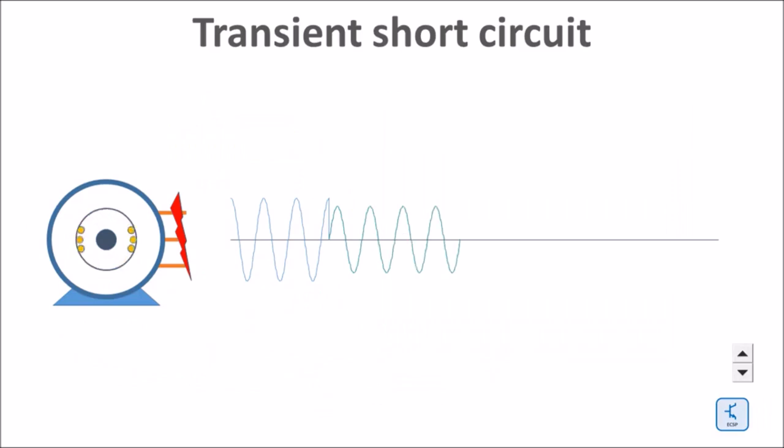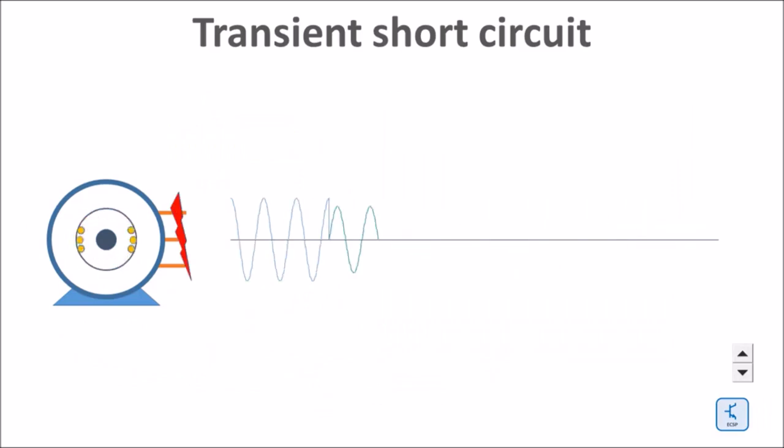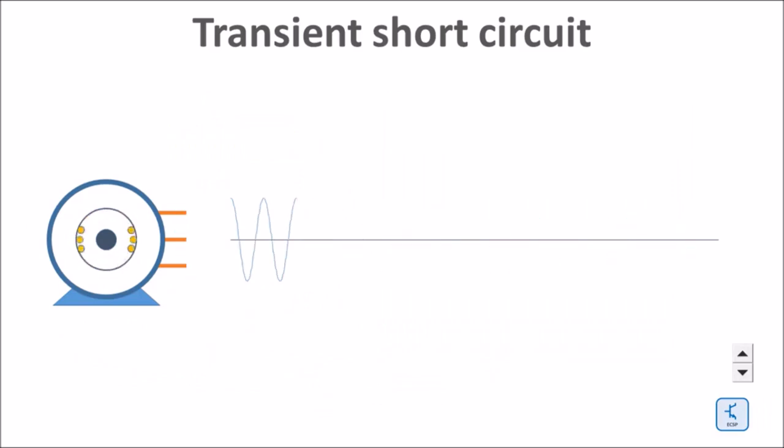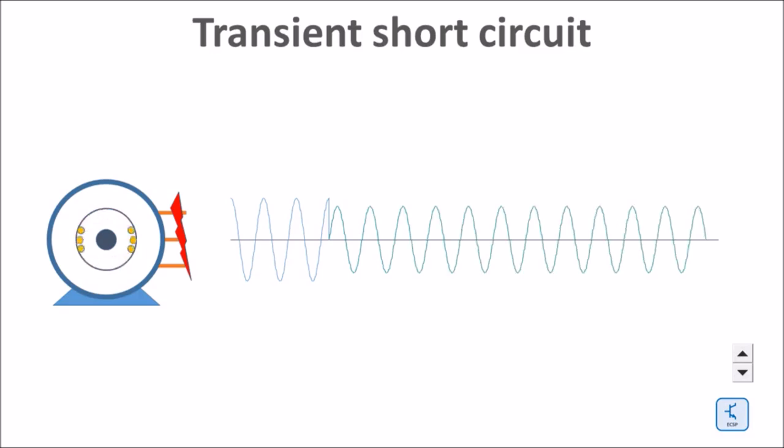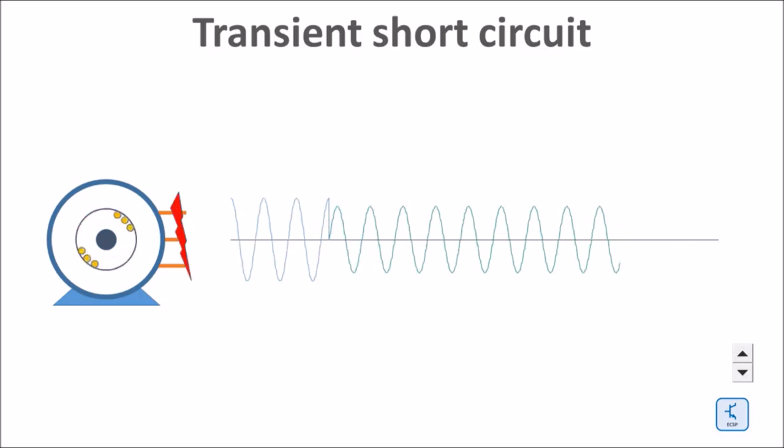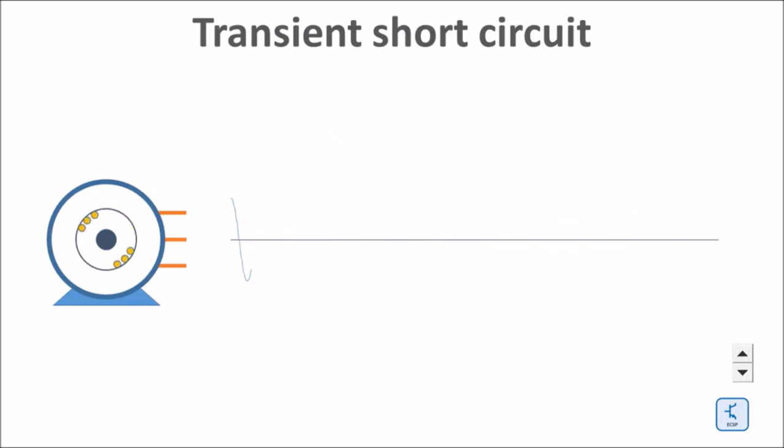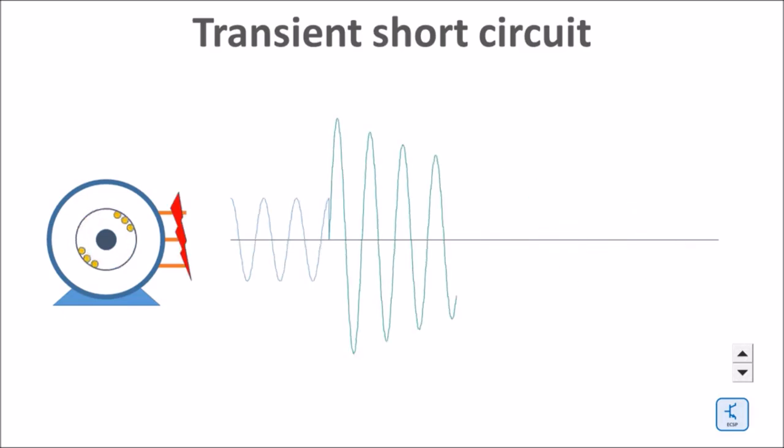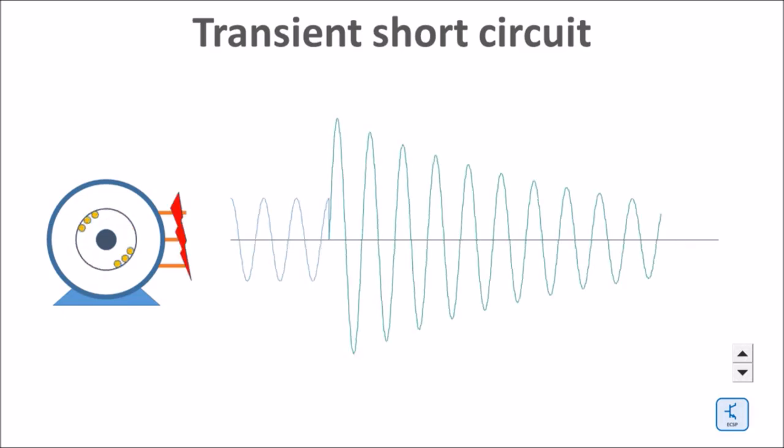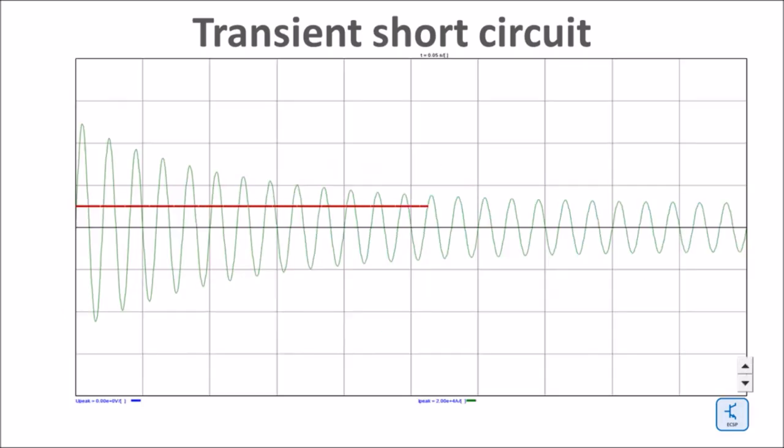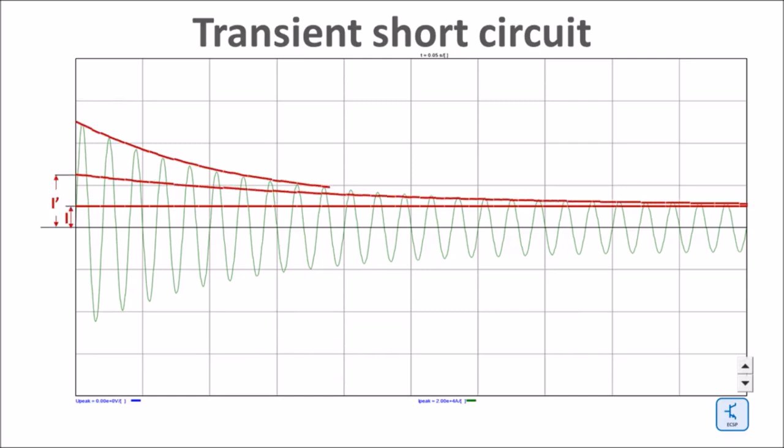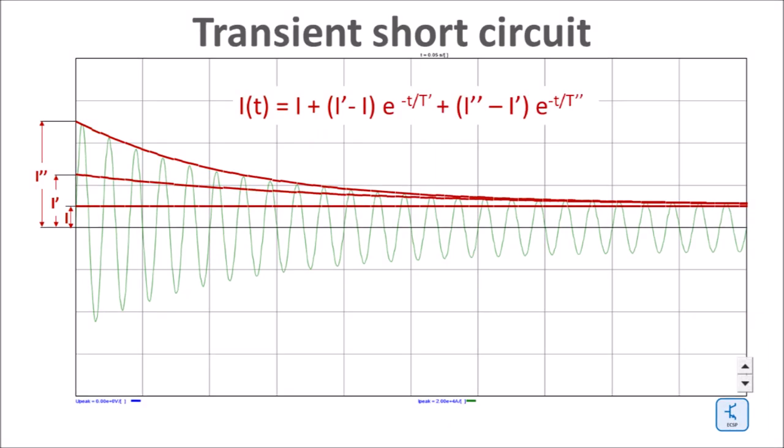One would expect that a short circuit close to an AC source would result in a steady short circuit current proportional to the voltage divided by the impedance of the source. What we see however is a much higher but rapidly decreasing transient short circuit current. It starts with a very high sub-transient current, evolving into a transient and finally into a steady state short circuit current.